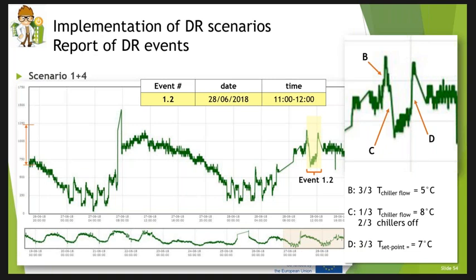So we were able to record a sensitive reduction of electric energy. And at the end of the event, at 12, we put the set point of the chillers back to 7 degrees, which is the nominal value for electrical chillers. So in this event, that day, we were able to lower the peak power demand by 20%.